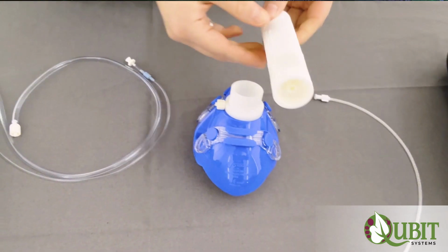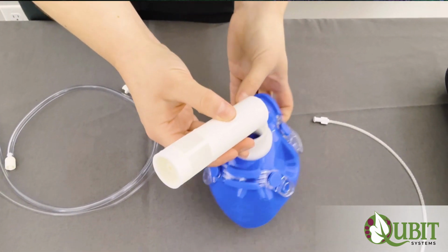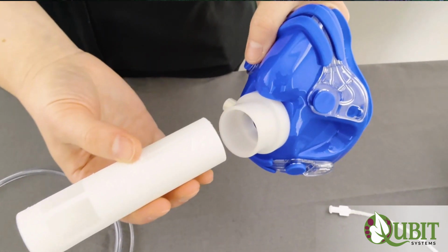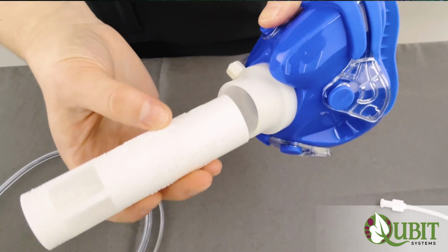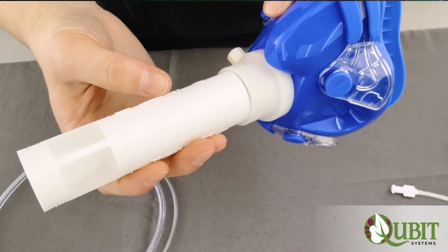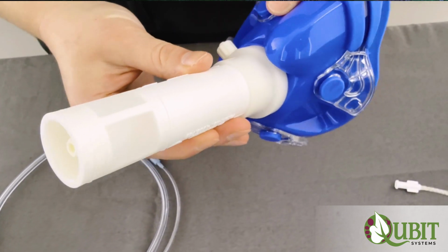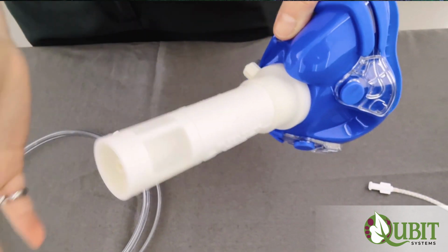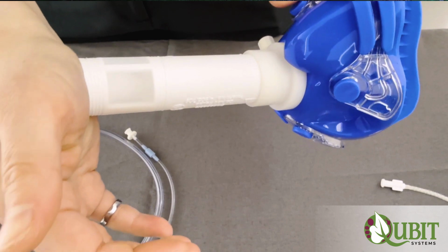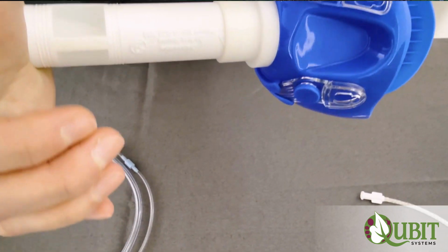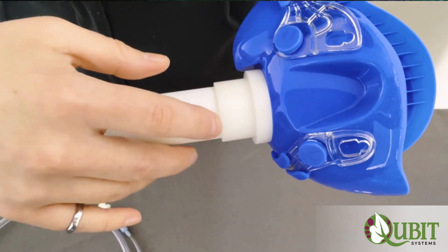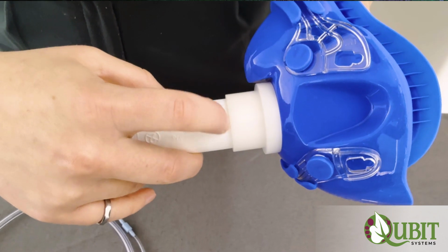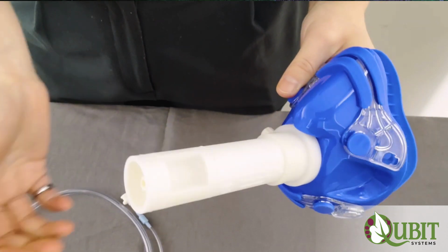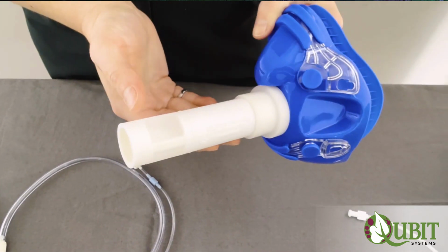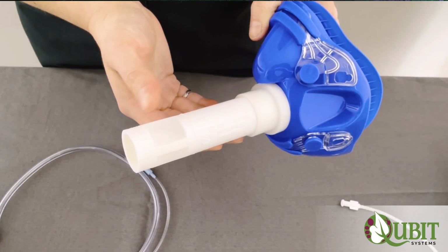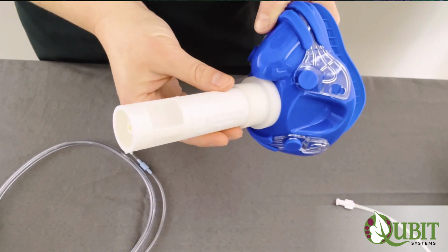Next, attach the PTAC, the pneumotach, to the PTAC adapter. It's important to push the PTAC all the way into the PTAC adapter. So first, place the PTAC, and then place your hand on the end of the PTAC and push in. When the PTAC is fully pushed in, it should cover about half of this triangle right here. It's important not to handle the PTAC by the screen, because the screen is what affects the calibration of the flow for the VOCO.